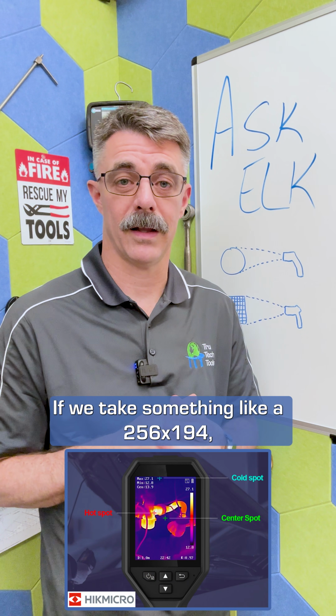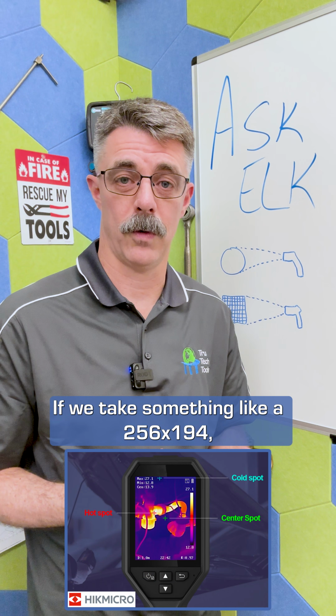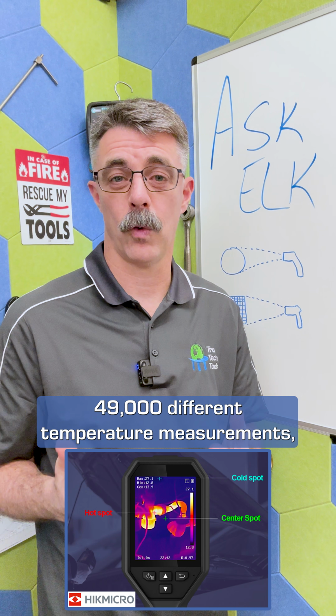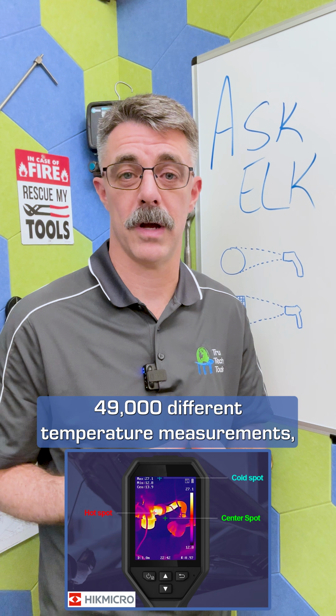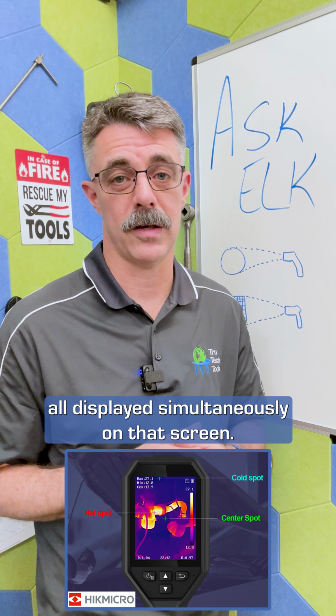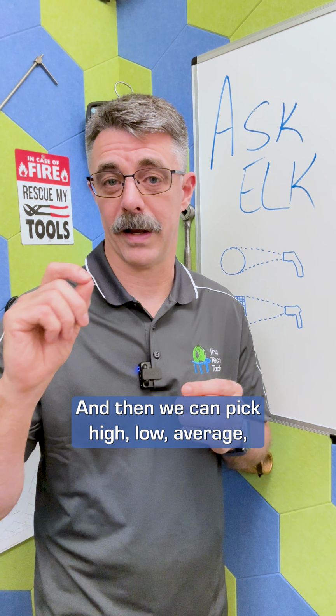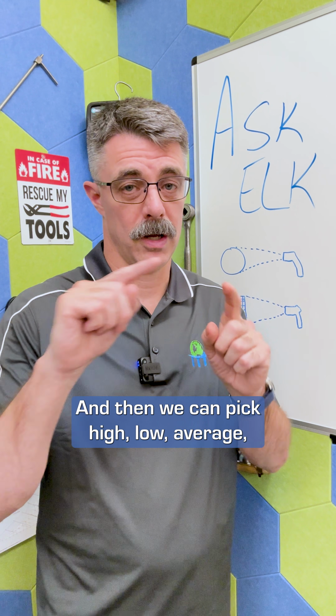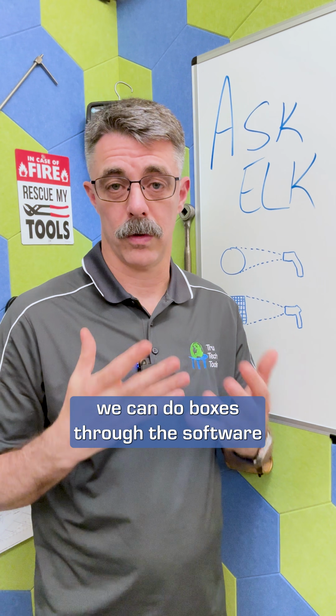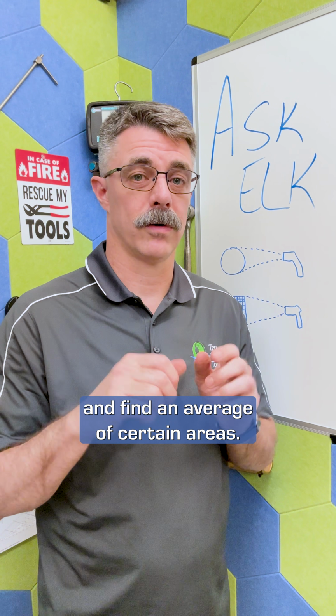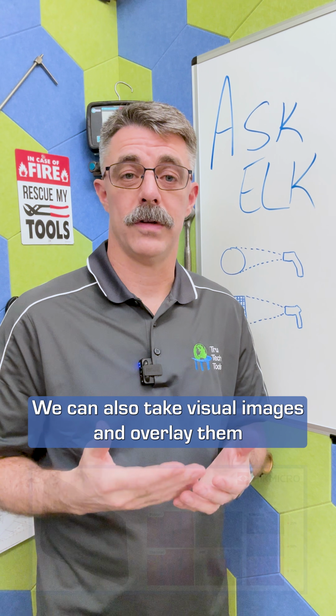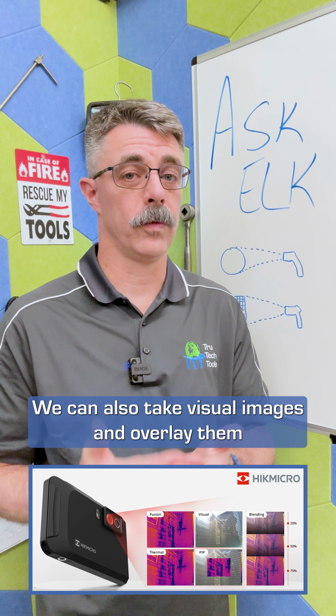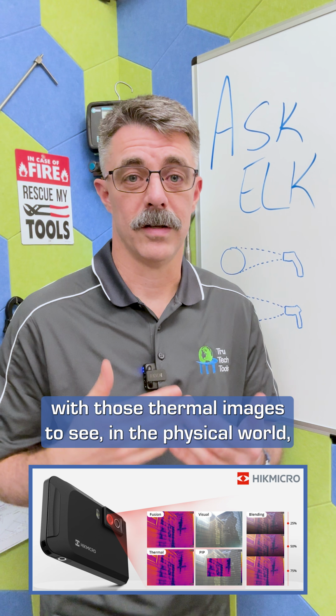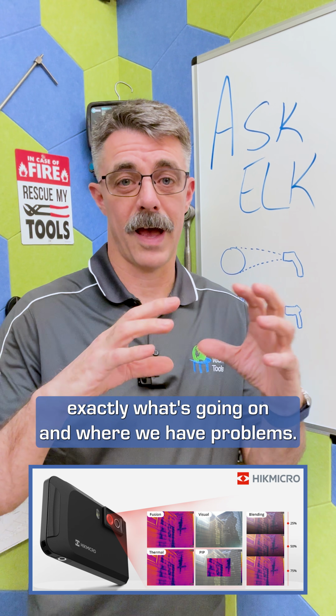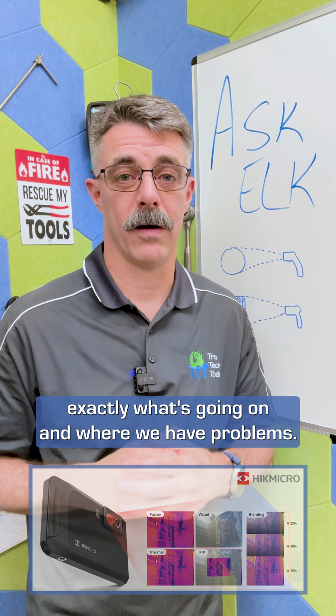If we take something like a 256 by 194, we end up with approximately 49,000 different temperature measurements all displayed simultaneously on that screen. And then we can pick high, low, average. We can do boxes through the software and find an average of certain areas. We can also take visual images and overlay them with those thermal images to see in the physical world exactly what's going on and where we have problems.